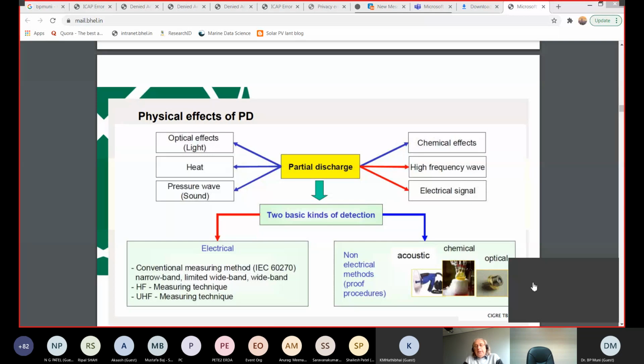So the PD activity and the damage produced by the PD depend strongly on the material. A gas is more resistant, and a ceramic support insulator is more robust against PD than a polyethylene cable, which normally doesn't accept any PD. That's a big difference: for transformers, a PD level of about 100 picocoulomb is allowed, in GIS about 5 picocoulomb, and for cable 1 or 2 picocoulombs, depending on the standard. It's the physics behind. Yeah, thank you.